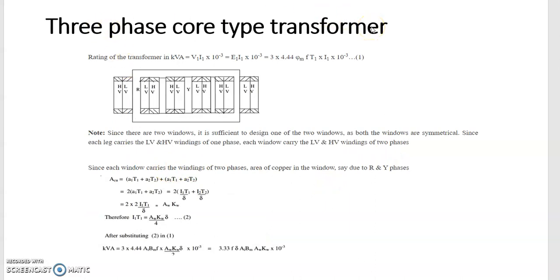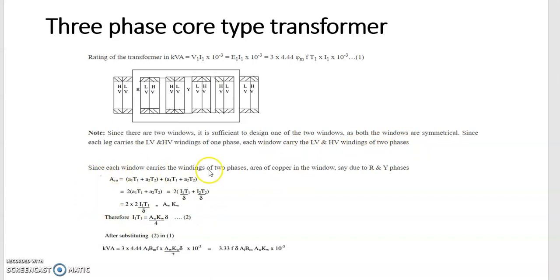Now talking about the 3-phase core type transformer. As you have already derived the equation for single phase, multiply the same equation by 3. Since there are 2 windows in the 3-phase core type, it is sufficient to design one of the 2 windows as both windows are symmetrical. Since each leg carries the low voltage and high voltage winding of one phase, each window carries the low voltage and high voltage windings of 2 phases respectively. This is the key difference between single phase and 3 phase.